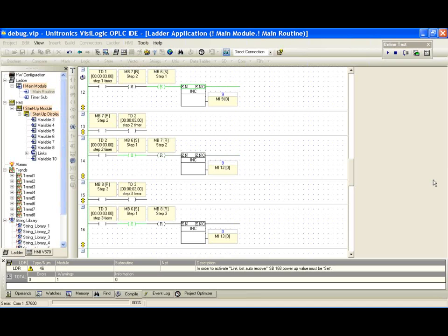And so I see some of you figured that out already by looking. That's great. Thank you. And now we have a tool that's showing us that this network was not activated. So let's go ahead and take a look at what is going on in this network, in this ladder. Again, maybe someone used a copy-paste function. When we use a copy-paste function, we remember that we've taken those specific variables that we've linked to. Maybe we like the structure. We've copied these 2 nets and pasted them down here. Maybe we just forgot to make 1 change.